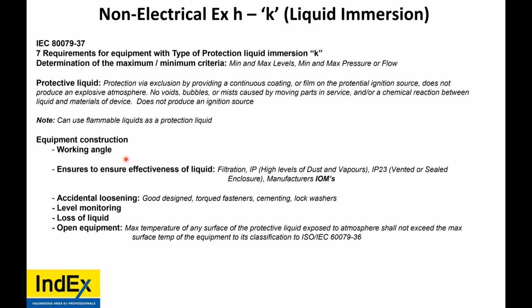Now, the equipment construction is important because what is its working angle? Is it going to be on a 45-degree angle? Is it going to be perfectly level with the ground? It needs to ensure the effectiveness of the liquid. It needs to be filtrated. It has to have a high IP rating of IP66 for when it's high levels of dust or vapors, IP23 when it's vented or sealed enclosure. And the liquid must be as per the manufacturer's IOMs and the standard and the certificate. It shall avoid accidental loosening via good design, cementing, lock washers. You need to monitor the level of the liquid. You need to monitor for loss of liquid, or to ensure there is no loss of liquid.